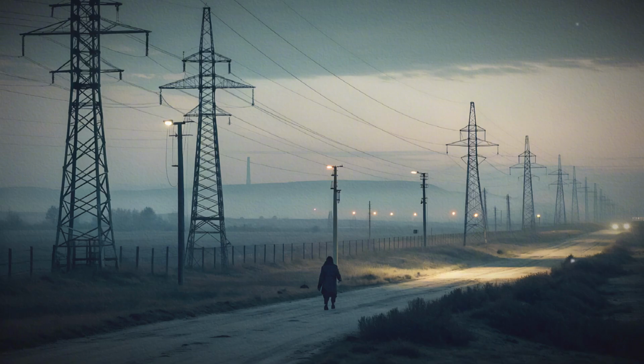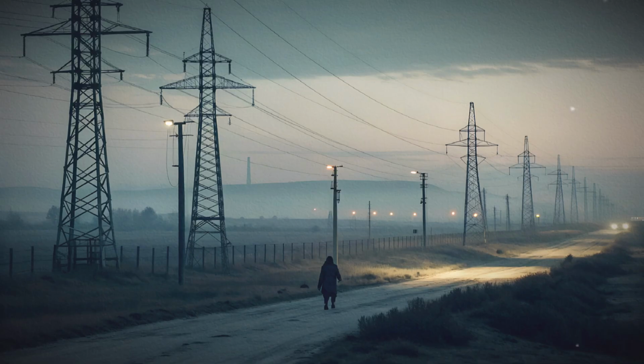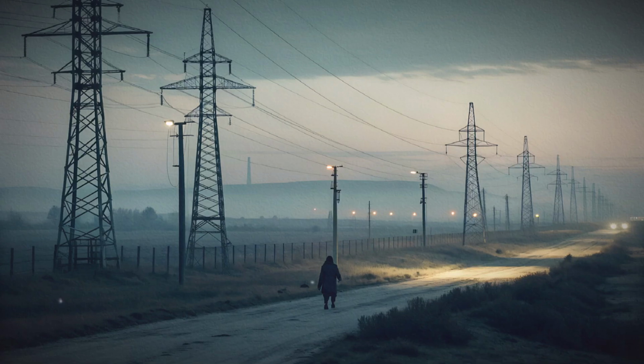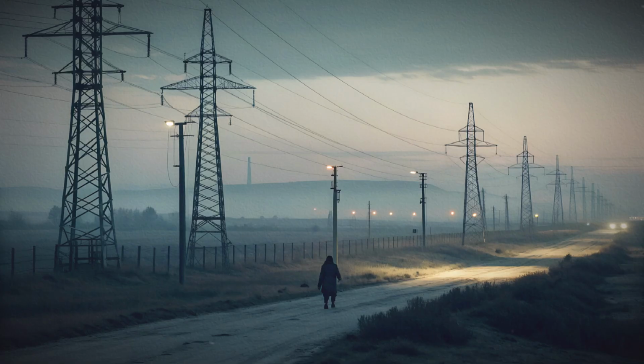Electrical flow on transmission lines is alternating current in most regional grids. Alternating current allows transformers to change voltage levels with relative ease. It also supports synchronous operation across wide areas, which simplifies the sharing of generation among multiple sources. AC transmission, however, introduces reactive power. Reactive power does not deliver net energy, but affects voltage levels and the apparent power flowing on the line. Managing reactive power is part of maintaining efficient operation.